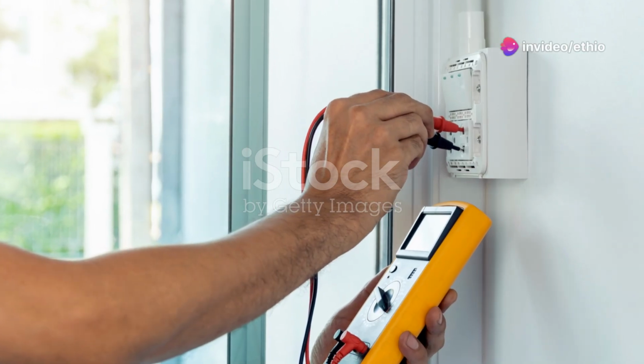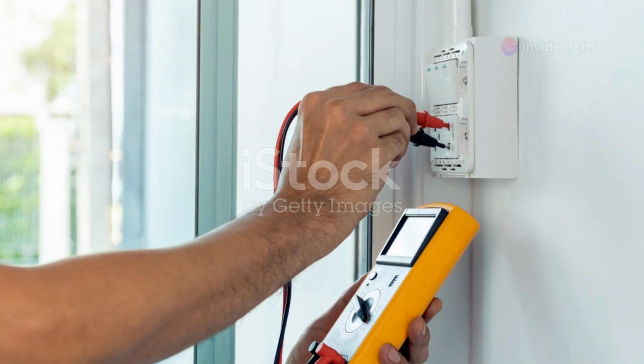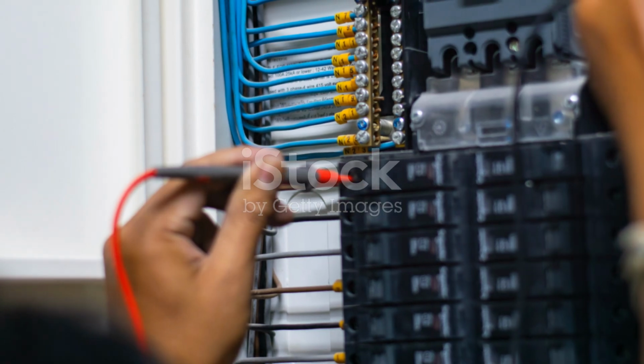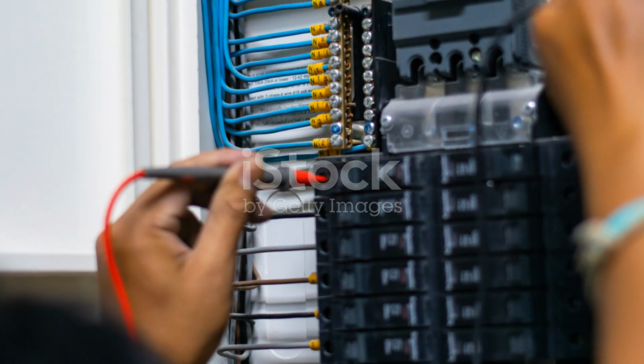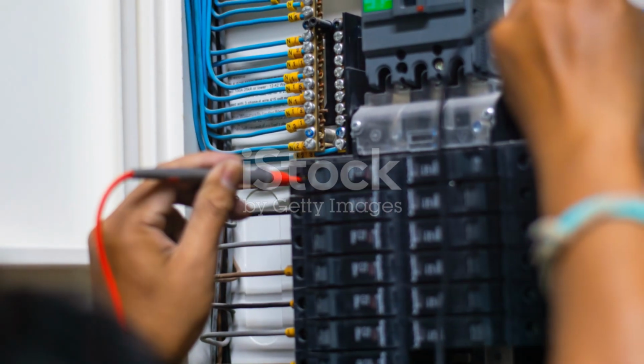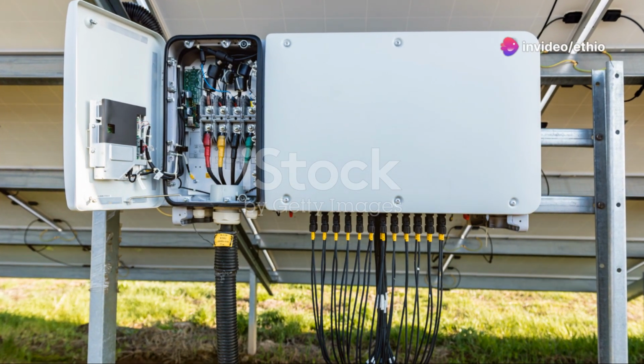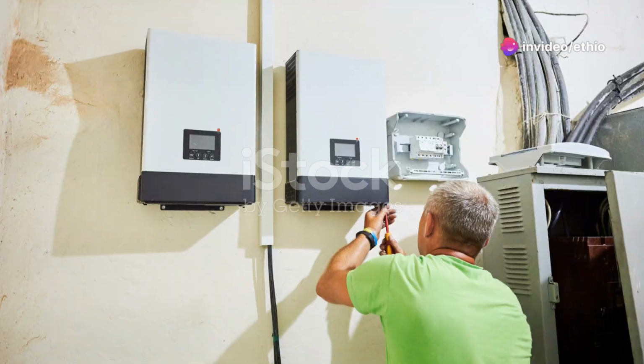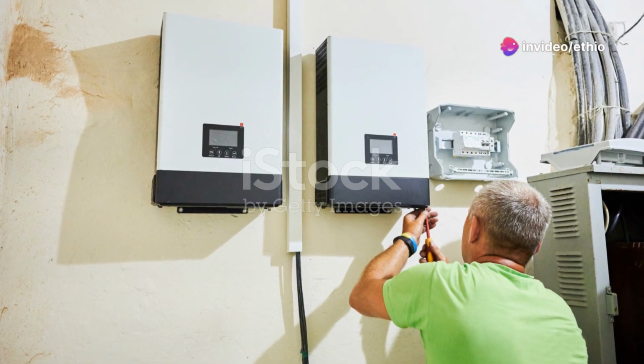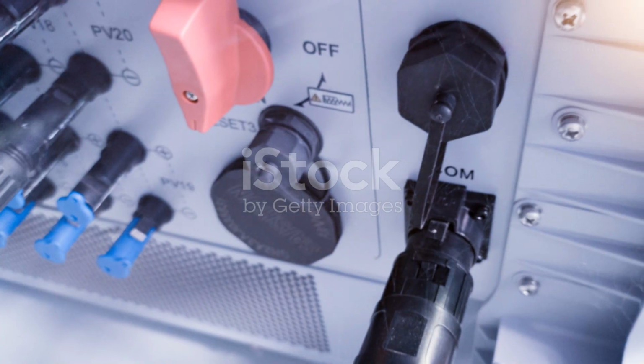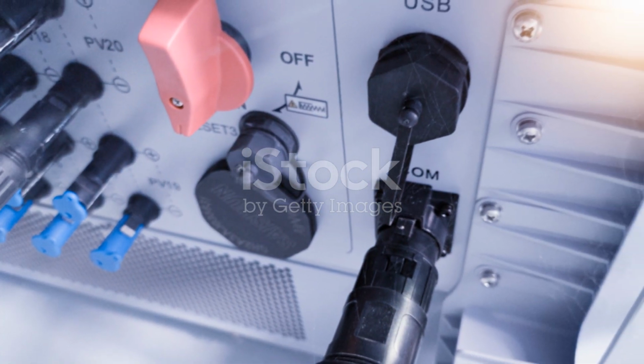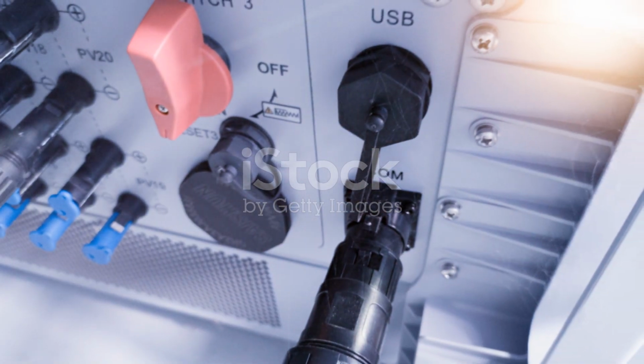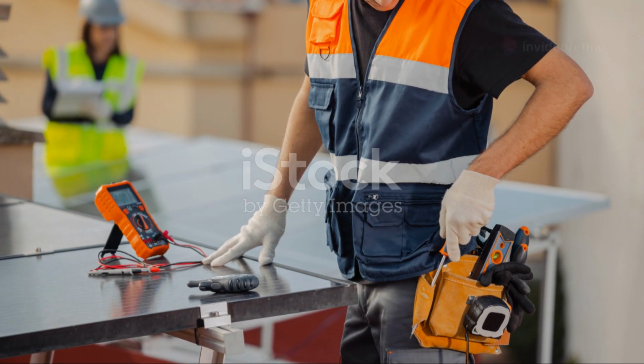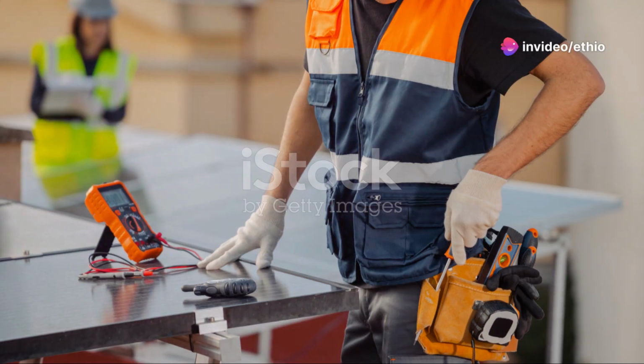If your inverter still isn't showing any power, grab a multimeter and measure the voltage coming from your solar panels at the inverter's input terminals. You should see a voltage reading close to your system's rated value. If it's much lower or zero, that's a clue. If there's no voltage at all, the issue could be with the panels themselves, a blown fuse, or even a wiring problem somewhere along the line.